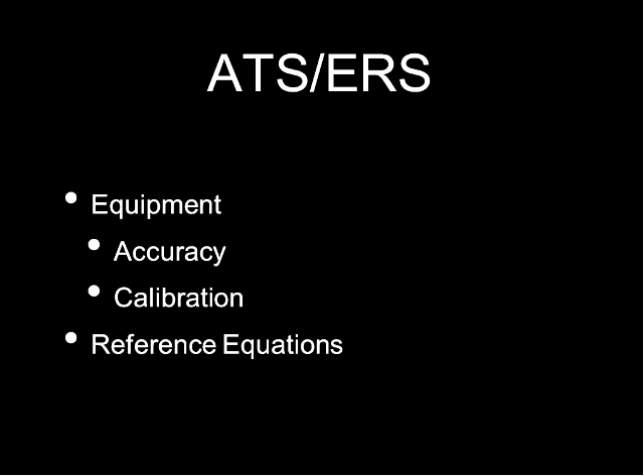Part of this is the confusion between calibration and calibration checks or calibration verifications. Most of the small devices used for testing at bedsides and elsewhere cannot be recalibrated in the field, but they can have their calibration verified to make sure that they're still operating correctly. We've done quite a few studies, and we have found some of the devices that, quote, never need calibration actually needed to be sent back because they'd been mishandled or abused and had gotten out of calibration. So you need to verify that the device is still working correctly before you just assume that the numbers you're getting out of it are correct.